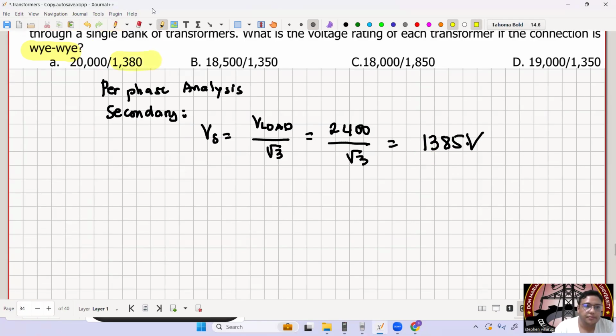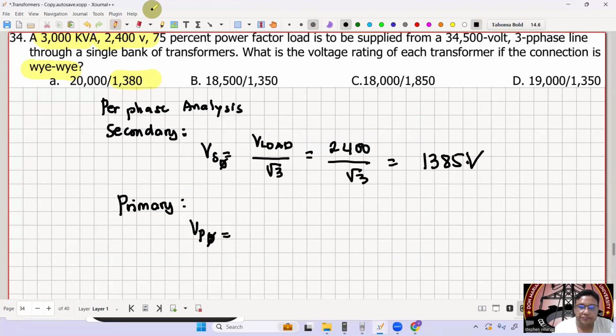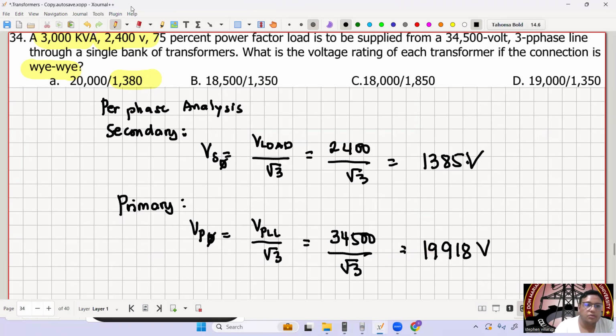Let's verify the primary. So for primary, okay, your V primary per phase is equal to your source voltage, so your V primary line to line over square root of 3. So this is now 34,500 over square root of 3. So this is equal to 19,918, or approximately that is 20,000. Letter A pa rin. So that is 20,000 over 1,385. So that's your number 34.